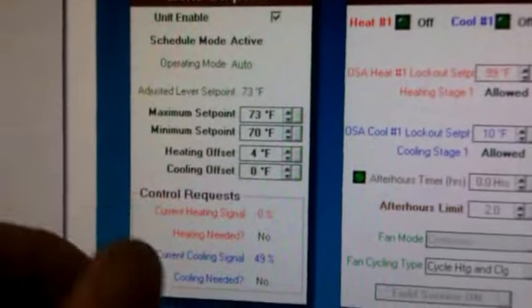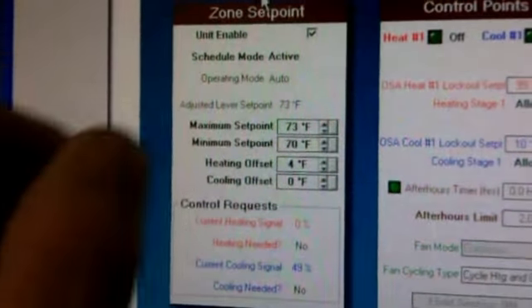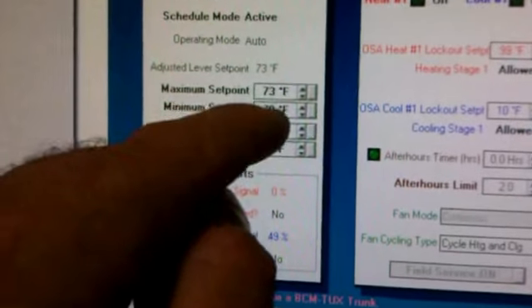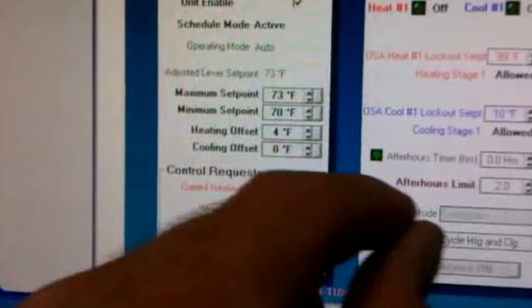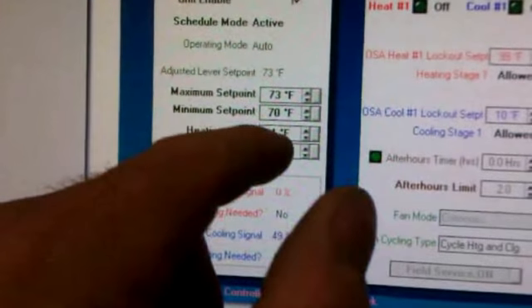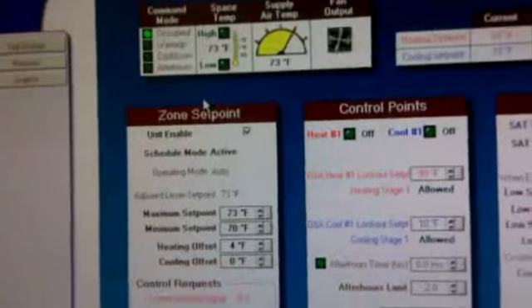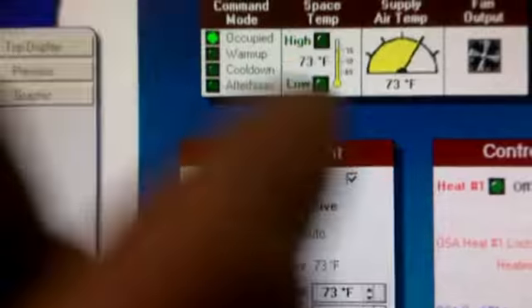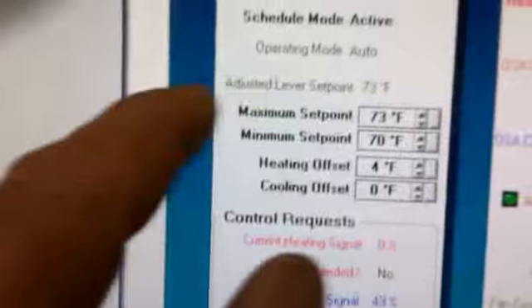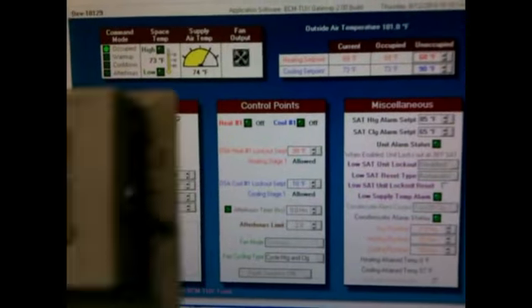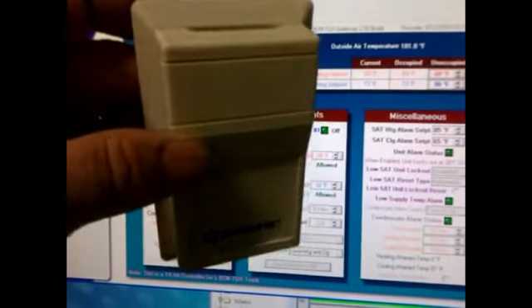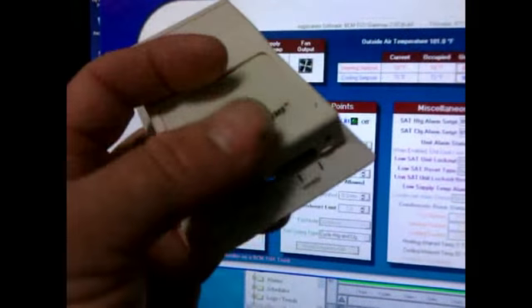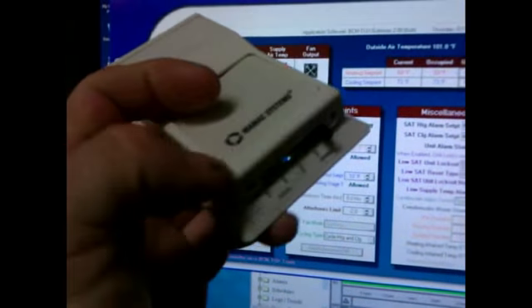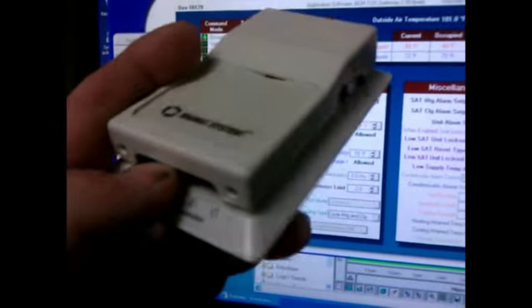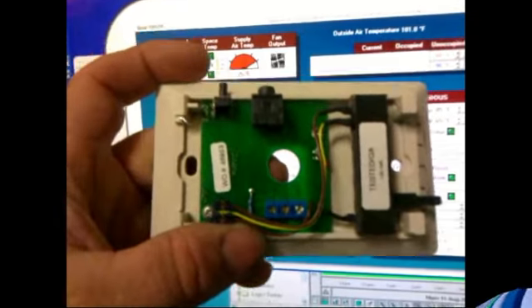Got the slider controls for them to set their temperatures in their rooms, and then we limit what the range is. So in this room, it's fairly cool: 73 degrees for the warmer range and 70 for the cooler, and then the heating is 4 degrees lower than that. Space temp is at 73. Adjusted lever set point is 73, which means those thermostats will look like this. Room sensors just have a slider on the bottom, warmer and cooler, just a potentiometer slider inside. Looks like that.